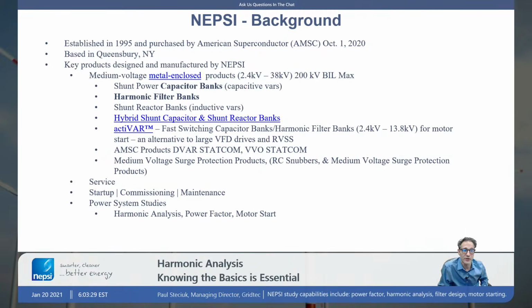We have an ActiVAR product, which is an inexpensive way to start very large motors. Sometimes we go up to 48 megavars. Remember that large motors, when they start, especially induction motors, they pull in a lot of reactive power. We can compensate that reactive power with a large capacitor bank. This is a more cost-effective solution when you compare it to, say, a large VFD drive or a large LCI drive. So motors up into that 5,000 or 10,000 horsepower range, and even up from there, this ActiVAR solution is a great way to start those motors using a simpler, less expensive technology.